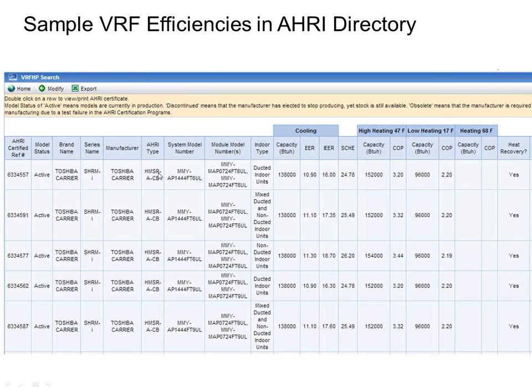The AHRI type, and remember the R means heat recovery system, so all 5 on this screenshot are heat recovery, and the A means it's an air-cooled or an air source system. The rest of the digits don't really matter for our purposes here. The system model number, then the module model numbers. So what that is, they recognize that you can take 2 or sometimes 3 of these outdoor modules, these outdoor condensing units, if you will, and bank them together on the same refrigerant network. And typically what the manufacturers do is they give that its own model number when I put 2 modules together, so that way it can have its own rating.